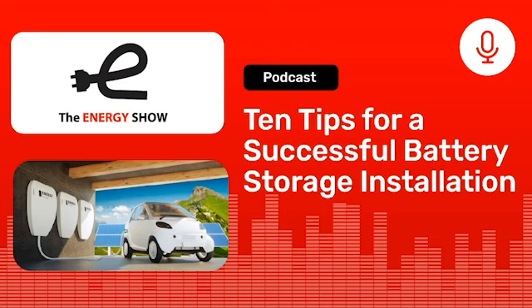In many cases you also need communications to the battery system. A lot of electricians are good at putting in thick number 10, number 8, number 6 wire, but a lot of these communications require installing Cat5 cable—it's a little different, you need different technology. And then you're going to have software on the other side of it, which we'll get to in a minute.